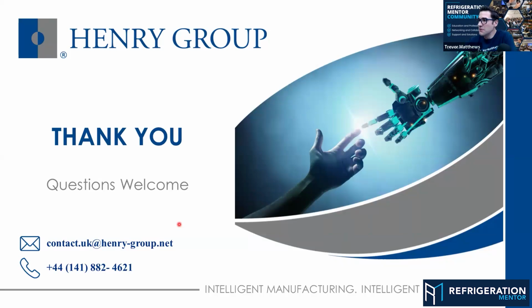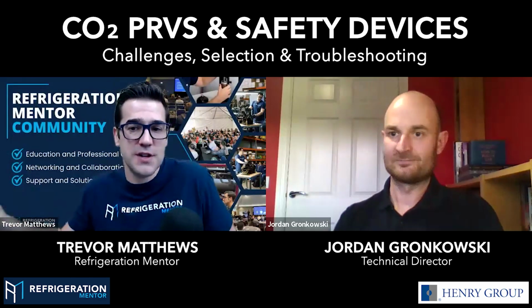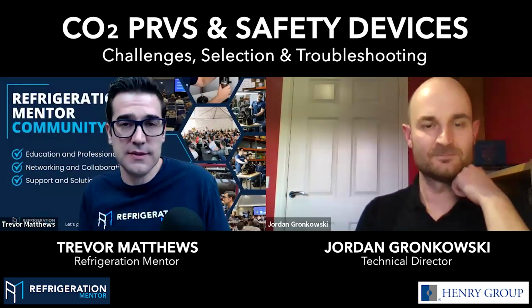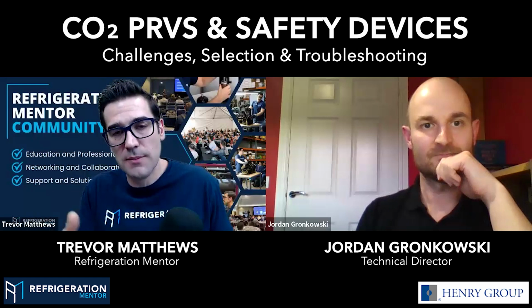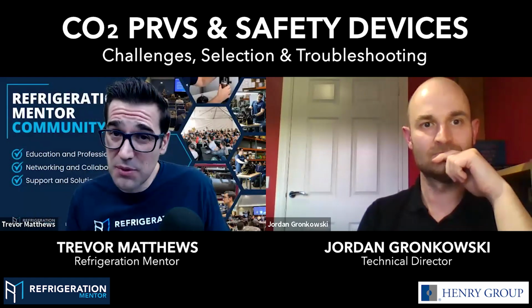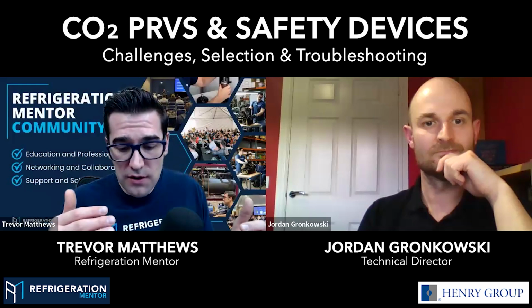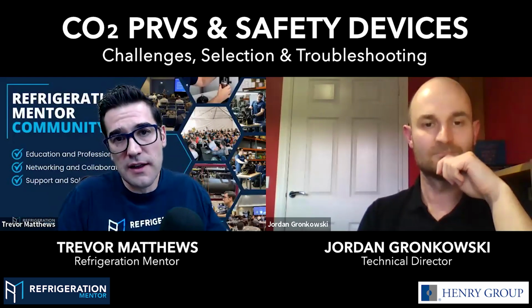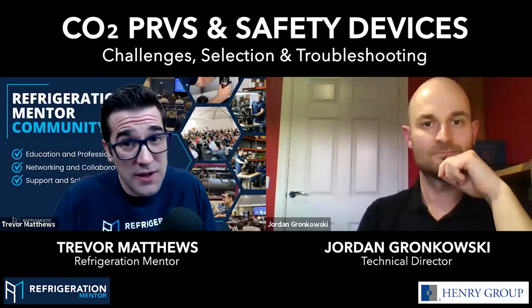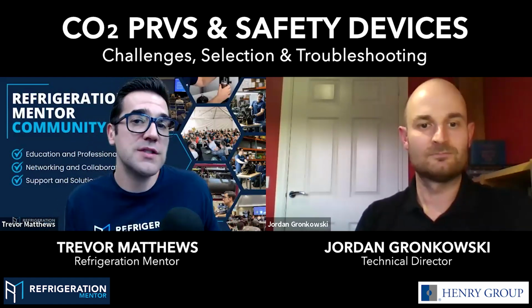Yeah, I definitely think you have the knowledge, and I really appreciate you taking the time to share with us, because this is a topic that a lot of people think pressure relief is boring. It's like, I don't need to know, that's the engineering stuff. But still, as a technician, we need to know this stuff. We need to have an understanding of every component in the system. When I'm doing CO2 trainings, because I've trained thousands of people in CO2 over the last few years, you need to know every component. Just because it's not a component that's working every day, but it is working every day. It's in place there for those times that the pressure does build up, or you have a catastrophic event, or someone closes the wrong valve. And this is not only for CO2 systems. This is HFC systems, HFO systems, industrial ammonia systems. So understanding this is very, very important.